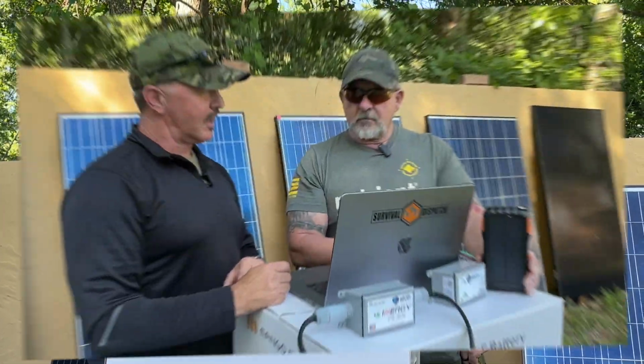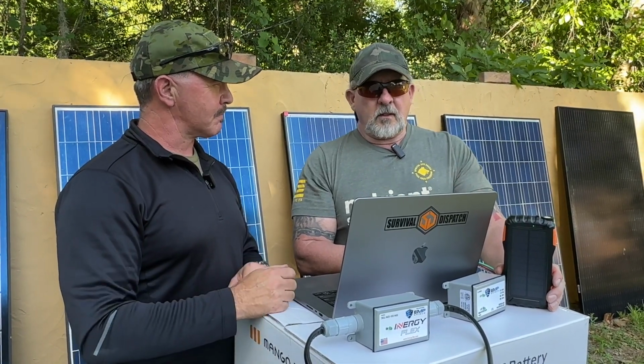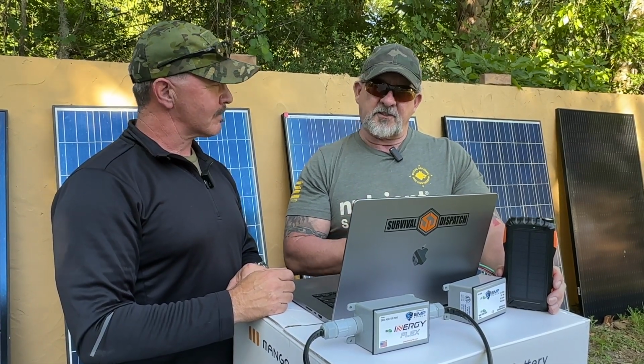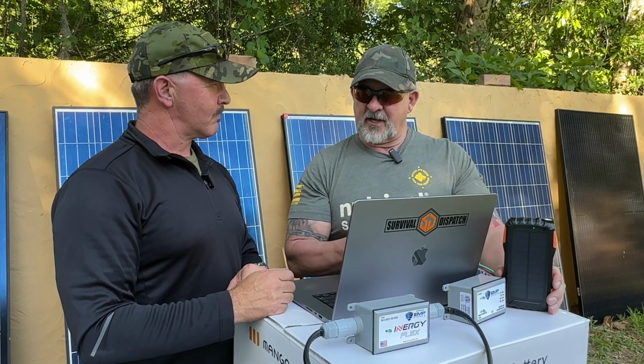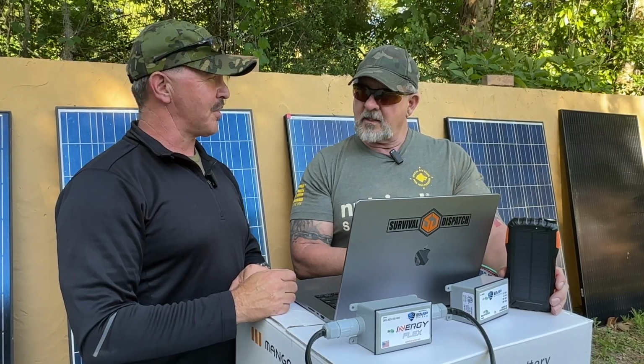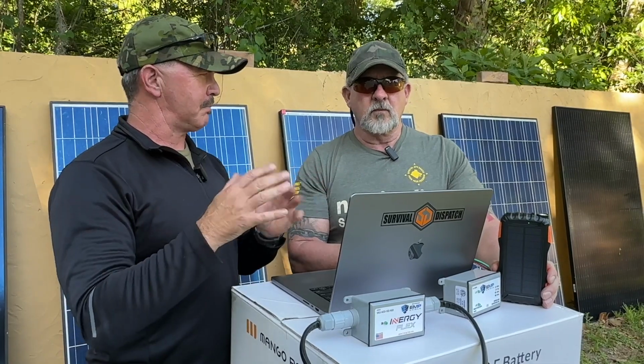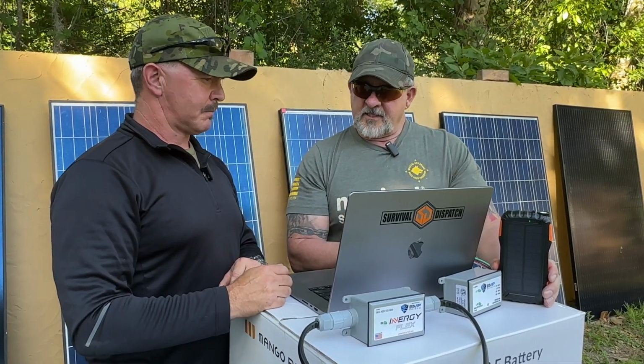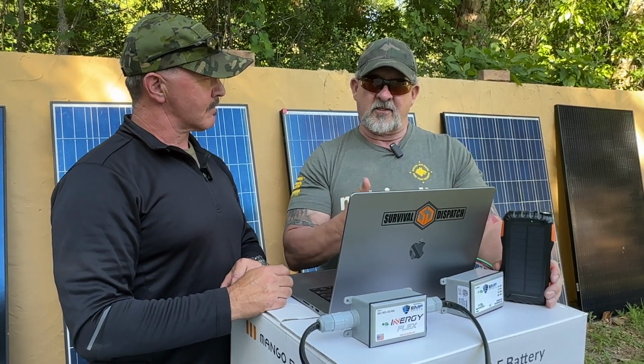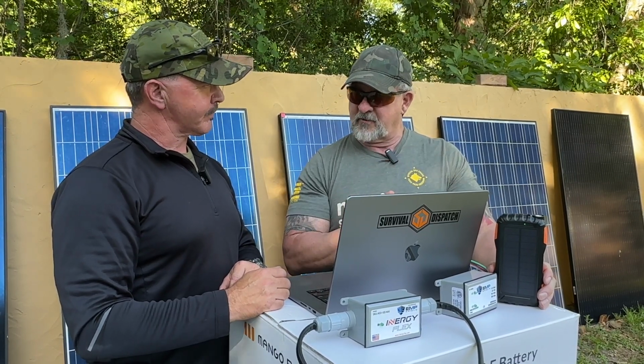All right. So Chris, what are we talking about in terms of charging cycles with these units here? So Mango advertises 6,000 charge cycles, but CATL advertises 7,000 charge cycles. So I think Mango's trying to err on the side of caution. You said 7,000. That sounds like a lot. What's that in terms of a time frame? You're looking at probably 10 to 12 years under normal usage. And at the end of the 10 to 12 years, it doesn't mean that the batteries are garbage. It just means that they're probably down in the 70% range.